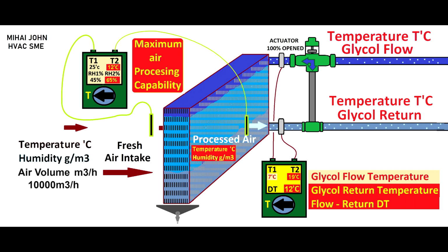A formal request for a comprehensive report regarding the integrity of the mainstream glycol flow should be made to ensure a thorough examination. Should the glycol mainstream flow be confirmed as sufficient by the chiller engineer, the AHU engineer should proceed with meticulous examination of the local strainer, glycol valves, and heat exchangers for any indication of blockages or other impediments.